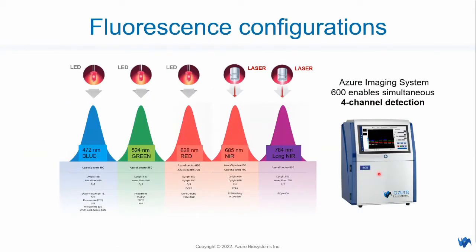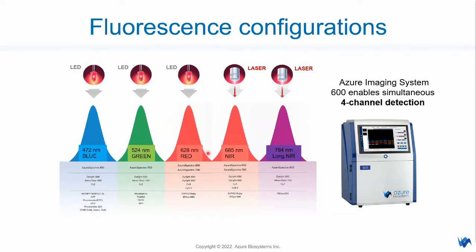Looking at the fluorescence configuration in the Azure Imaging System 600: RGB signals are excited through LED excitation light sources, and near-infrared signals are excited through laser excitation light sources. Even though we have five excitation light sources for fluorescence applications, we do not recommend five-channel simultaneous detection. We recommend four channels because the red channel and near-infrared 680 are too close to each other — there is a high possibility of crosstalk. For fluorescent multiplex western blot, we recommend either red/green/blue plus 784, or any combination except pairing the two red channels together.